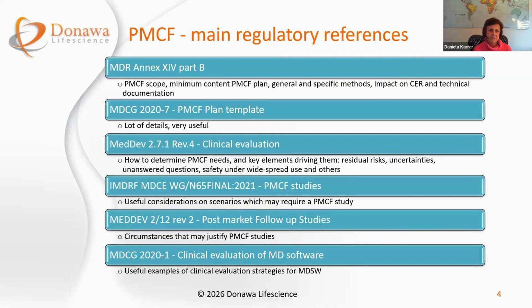I want to say something on the second document listed here. It's a guidance on how to write a PMCF plan template, which contains a lot more details on how the plan should be completed. It's a lot of details. It's good reading quite early, I think, because it puts you in the mindset of what are the questions that at some point in the development of the device, if you reach the market, you'll need to answer.